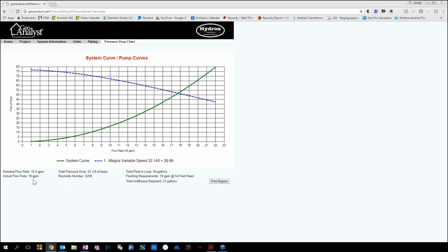So I'm not sure. Yeah, see here, they are showing us running both pumps. We will be running a 2699, and a 32140 will handle whatever the 2699 can't cover. And together they'll give us 18 gallons a minute on that ground loop and pull our Reynolds number up over 2,000. So just showing you the example, 32140 alone would give us the proper flow but low Reynolds. That's your call whether you want to install that with a 32140 or 2699.